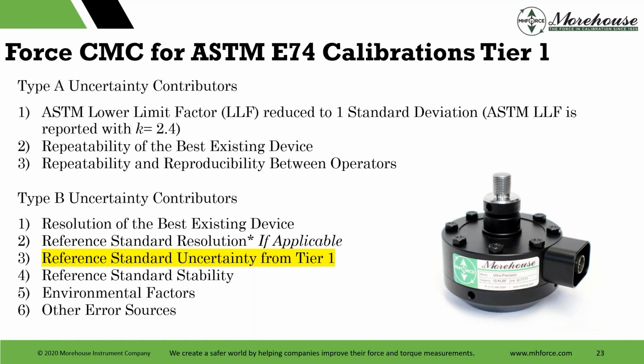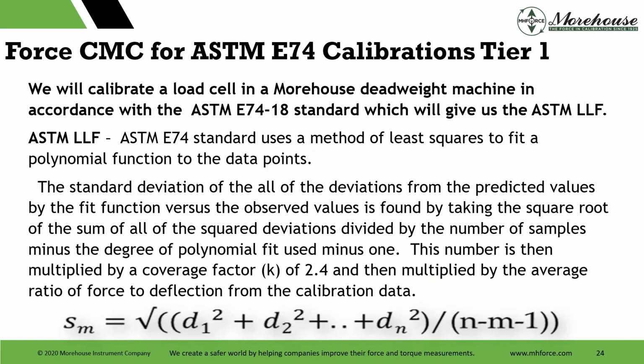There's the same slide I showed before, and basically on this one, we're just saying, okay, these are what we're doing here. We're going to take that tier 0, and we're going to calibrate a load cell. And we're going to hopefully calibrate it in accordance with E74, which gives us a really good reproducibility condition of the instrument, which is going to become one of our major components for uncertainty. And we calibrate that cell in a deadweight machine using ASTM E74. The latest standard is 18. It does need revised, and that's going to give us a lower limit factor. That lower limit factor standard uses a method of least squares to fit the polynomial function to the data points.